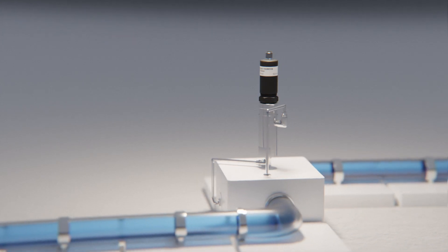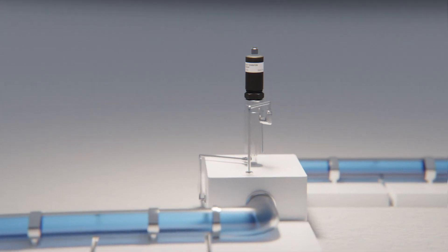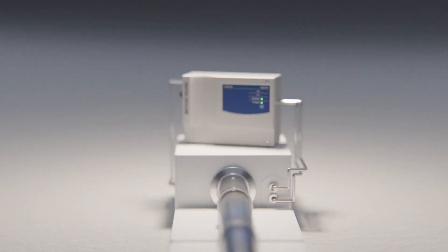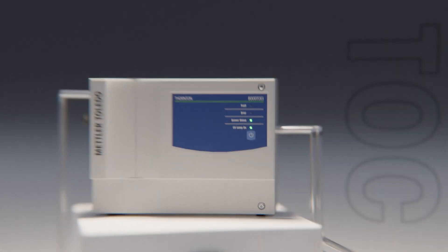Resistivity can also detect organic acids and bases, but it can't detect the majority of organic contaminants, making it important to continuously monitor TOC levels to prevent organic material from reaching downstream processes.